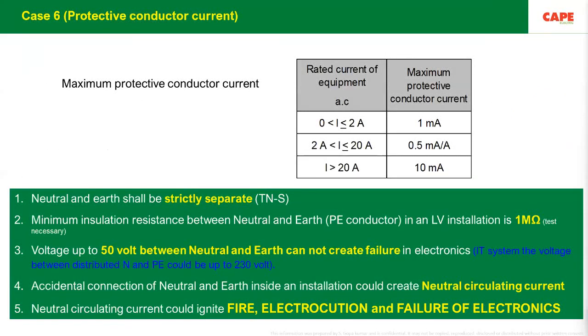Now, case number 6. Every leakage of current from an electrical installation will be seen through the earth, through the metallic parts of a building, as a current flow. Ideally, the current flow through the metallic parts must be zero, but due to leakages there can be a current flow, and this current flow must be limited. Otherwise, it can create a fire. In one incident, somebody from a top leading company called me saying my battery rack is creating sparks. What could be the reason? Very easily we could find out that it was due to a leakage current.